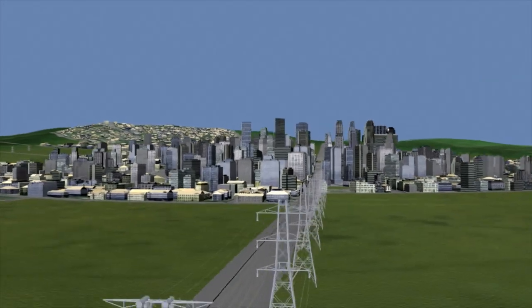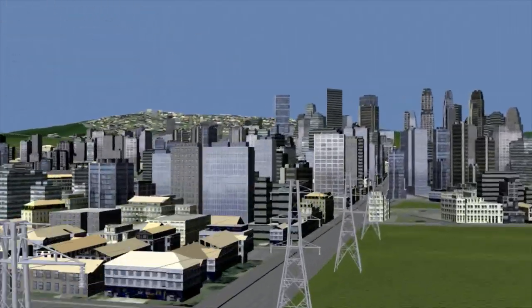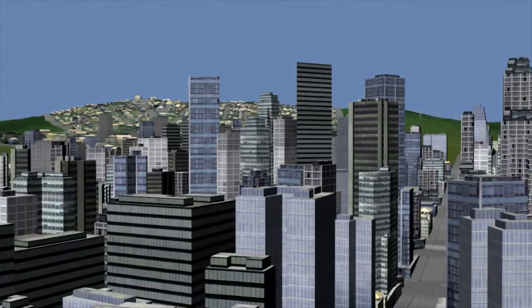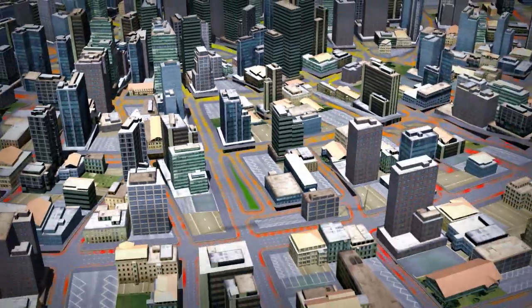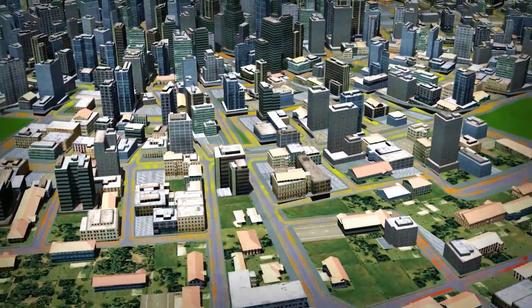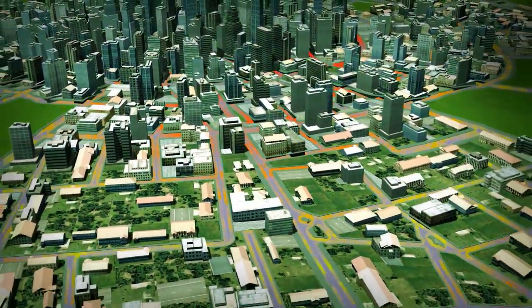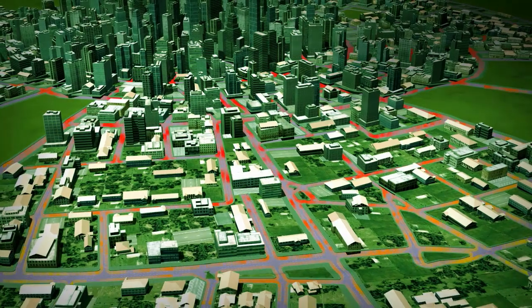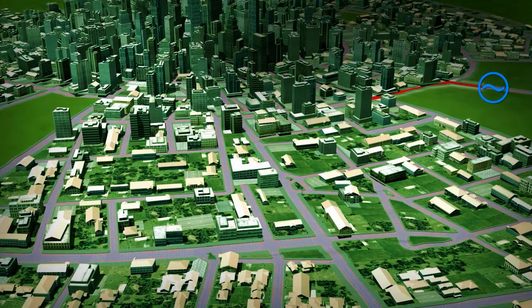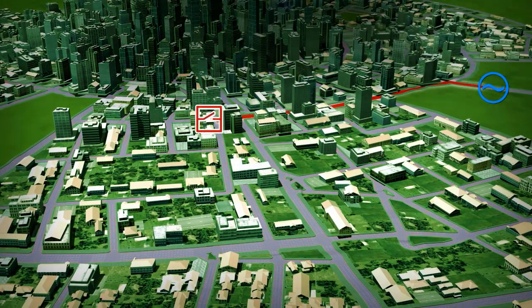The distribution lines are the pillar of any electricity network, distributing medium voltage around the grid. Distribution lines are used to deliver energy around the grid at 10 to 38 kV, and when a problem occurs, re-switching the network enables the supply of energy from an alternative source to maintain the supply.